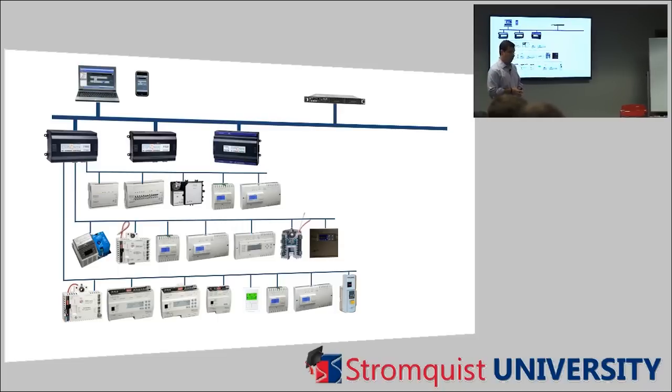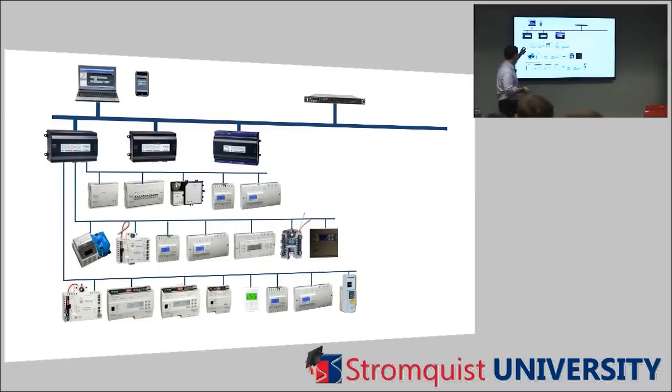You could have N2, you could have a Delta on the bottom, you could have a Honeywell on the top, correct? All the same building. Well, also remember too that the Jace can accept all, like in this scenario, I should probably take those off. They're just up there. They're not connected to anything. They're just there for looks. You'll notice that all this is wired back into this one Jace, and it's all different. So the whole point is that all these different languages, communication protocols, all go back into that one Jace, and the Jace does the translation for them and spits it out. So if you have different Jaces, they're all going to communicate together if you have one or two or three in a building? Right.